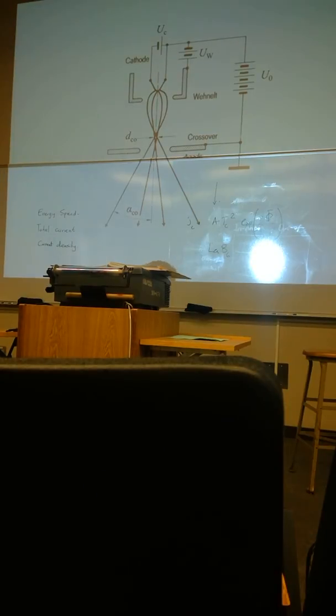In the old days, you had to keep taking out this Wehnelt and changing the filament, making sure the filament is centered on the hole of the Wehnelt cup. If it's not centered, obviously that will be distorted and produce real poor performance. So you have to make sure it's centered, put it in there, align it, and put it back.